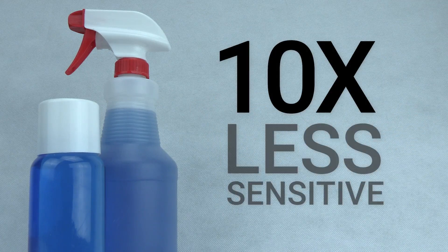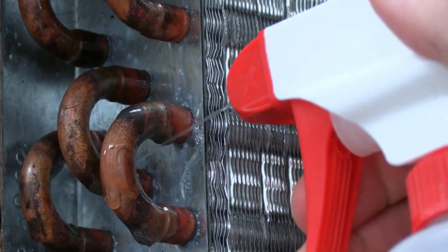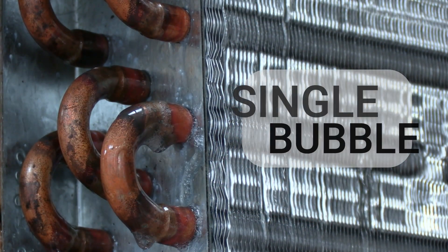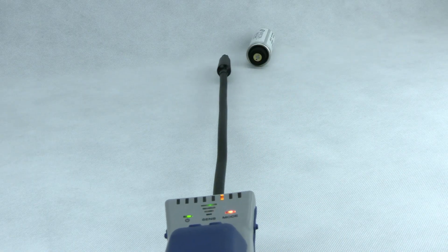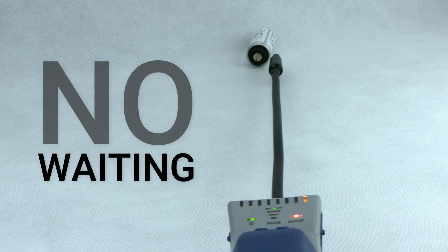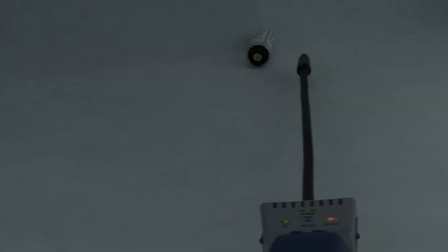At these smaller leak rates, it can take several minutes to form just one bubble big enough to see, where an electronic detector will find the leak almost instantaneously. With soap bubbles, you won't always be able to reach or see the suspect leak area.